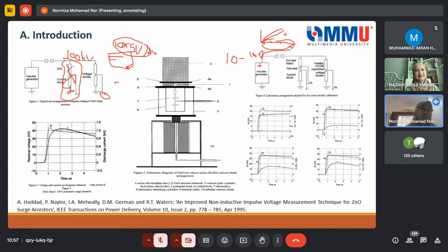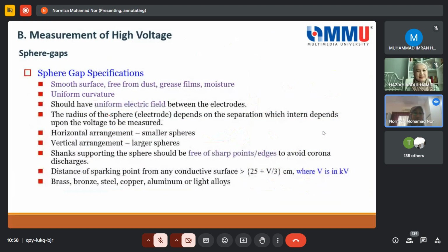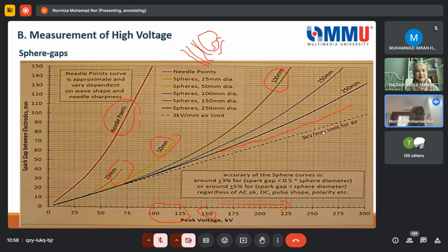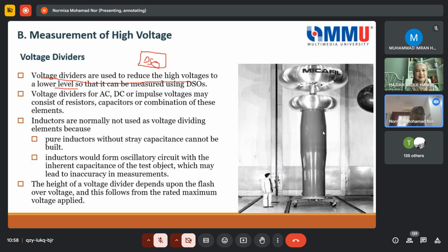So you can only measure with the oscilloscope up to 50 volts. So you have to bring this 100 kV down to only 50 volts. That's why they use the voltage divider. So here the voltage divider reduces the high voltage to a lower value so that it can be measured using the DSO. We've seen the example just now: 100 kV to be measured with 50 volts of DSO.